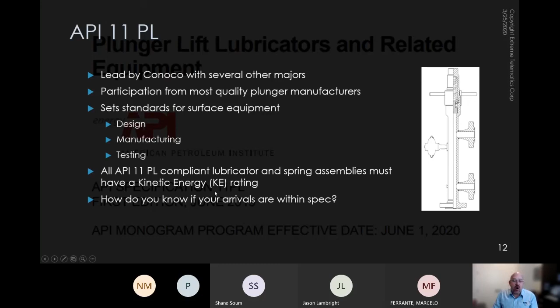It's not just a one size fits all. So if people want a higher grade of equipment or a lower grade of equipment, they can buy that, but at least they know the standards to which it was manufactured, designed, and tested. And it's no accident that the most common or the key factor that's stamped on the side of these lubricators is a kinetic energy rating. So now we actually have a measurable number that we know whether our plunger arrivals are within spec. And so you have to actually measure kinetic energy or the velocity to be able to get kinetic energy to know if your lubricator is being operated in a safe parameter.